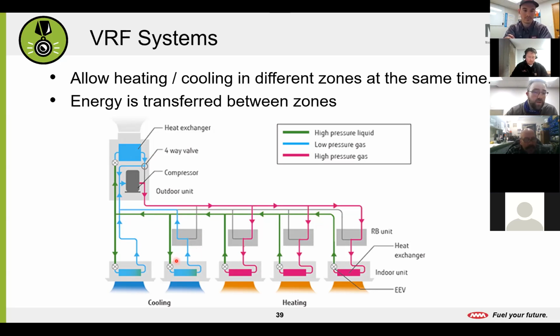But because we have 2 zones in cooling, we can actually pull some of that heat energy off and utilize that for our cooling zones. So where we have our medium temperature liquid coming back, we have 2 zones in cooling that say, hey, I want some of that, I can use that without having to send that to our outdoor unit to expend more energy to create more hot gas. I can just utilize what we already have. And so it'll pull that liquid in to our coil. It goes through what we call a metering device, this little X right here, and that drops the temperature from a medium temperature liquid all the way down to a low temperature vapor.